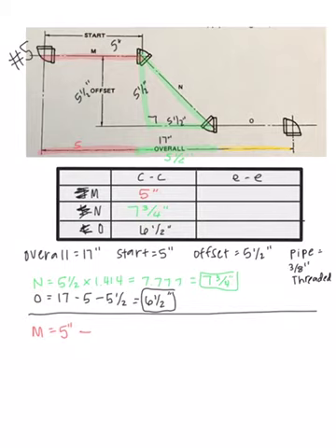And the takeoffs for a 90 and a 45 are 1 inch for the 90 and 3/4 inch for the 45. And you have to be careful on this one. A 3/8 inch fitting is so much smaller that its thread-in is not a 1/2 inch. It's actually 3/8 inch. So make sure you're looking carefully at data table 5 when you're doing your thread-ins.